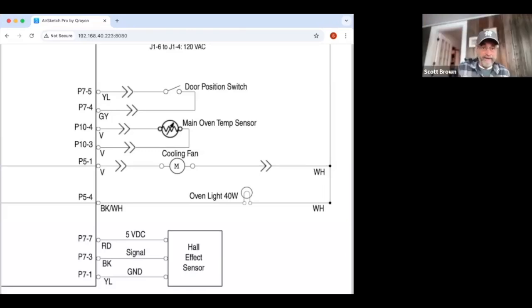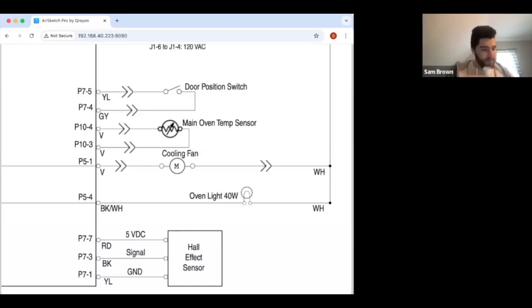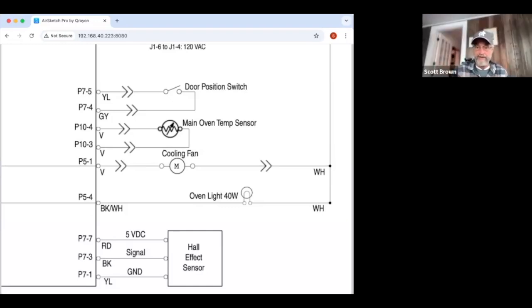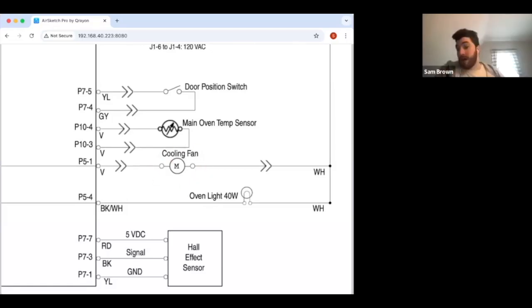So it's interesting, the difference between looking at a schematic and looking at the actual machine. The physical reality is different from the electrical reality. The wiring diagram may show the wires all going to the same component, but the schematic, because we're looking at circuits, shows them as separate. The Hall effect sensor, in this case for the cooling fan, is used by the board to monitor that rotation and to be able to throw an error if the cooling fan's not running, or not running at rated speed, because if it's not, it has the potential to cook itself.